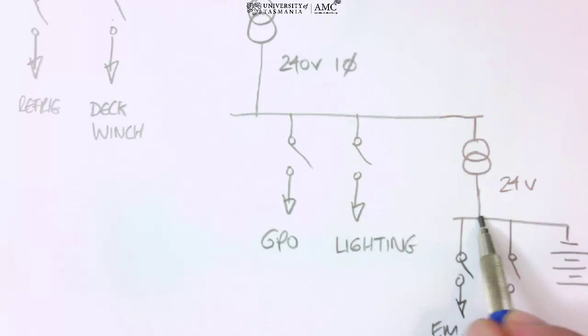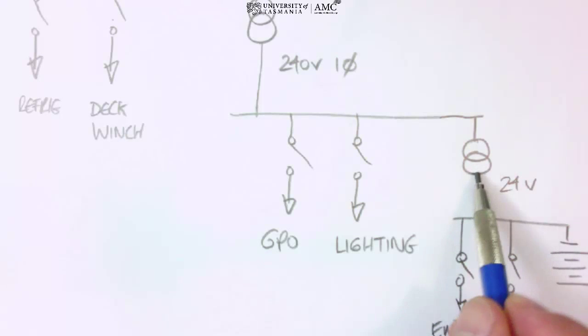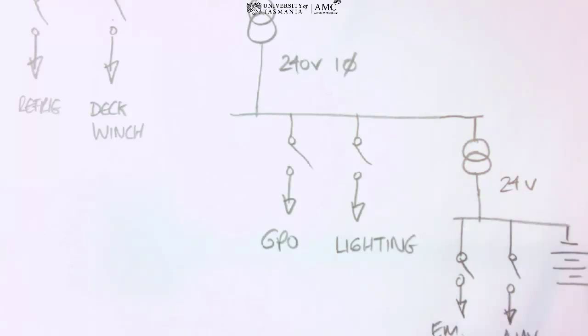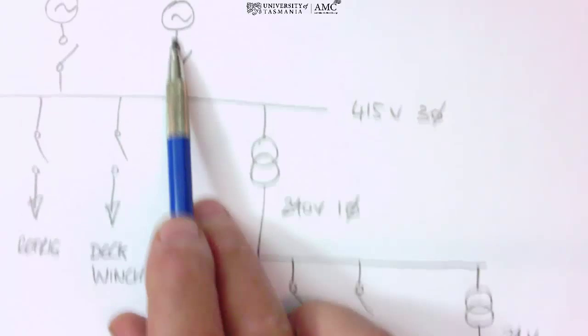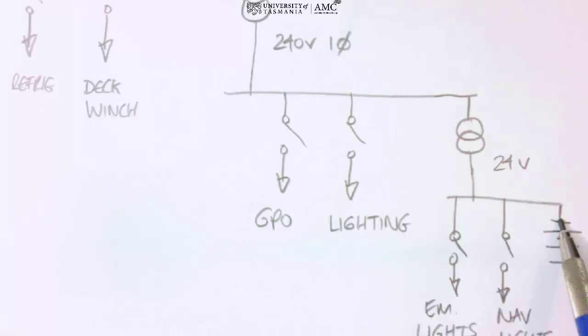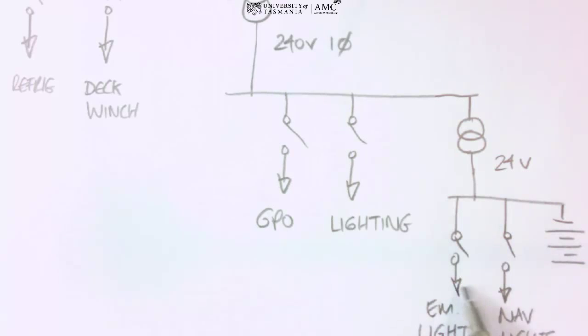Often this is the way this system works, that it runs on the higher voltage. We set our transformer slightly higher voltage than what our battery voltage is, and the supply will be from the transformer. And in the event of a blackout, if we lose our genset or gensets for any particular reason, then we automatically have DC power straight from our batteries to our emergency systems. And this is called a bumpless transfer. So in the event of blackout, we don't have to wait for any changeover. There's no interruption in power. The power just comes straight through to our system.